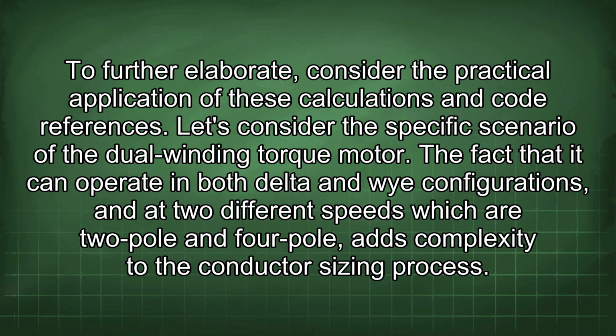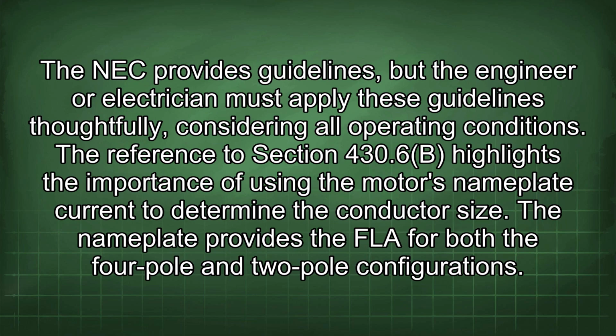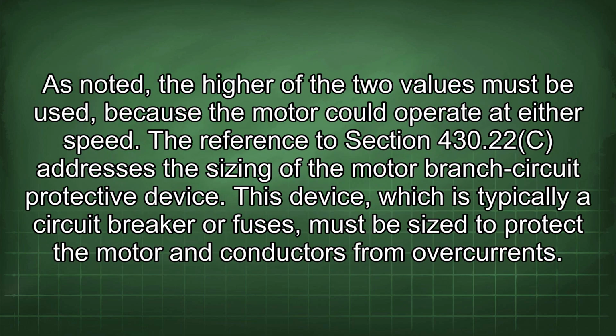To further elaborate, consider the practical application of these calculations and code references. Let's consider the specific scenario of the dual-winding torque motor. The fact that it can operate in both delta and Y configurations and at two different speeds, which are 2-pole and 4-pole, adds complexity to the conductor sizing process. The NEC provides guidelines, but the engineer or electrician must apply these guidelines thoughtfully, considering all operating conditions. The reference to section 430.6b highlights the importance of using the motor's nameplate current to determine the conductor size. The nameplate provides the FLA for both the 4-pole and 2-pole configurations. As noted, the higher of the two values must be used because the motor could operate at either speed.